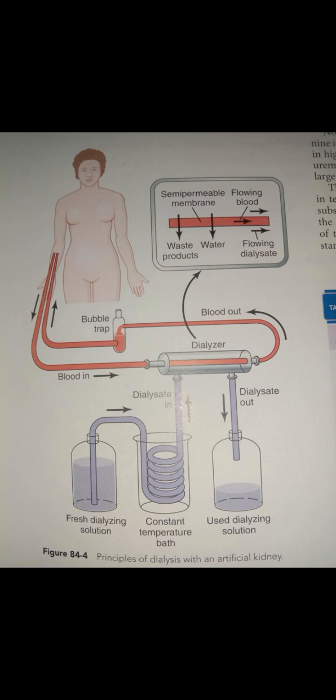In normal operation of the artificial kidney, blood flows continuously or intermittently back into the vein. The total amount of blood in the artificial kidney at any one time is usually less than 500 ml. The rate of flow may be several hundred milliliters per minute, and the total diffusion surface area is between 0.6 and 2.5 square meters. To prevent coagulation of the blood in the artificial kidney, a small amount of heparin is infused into the blood as it enters the artificial kidney.